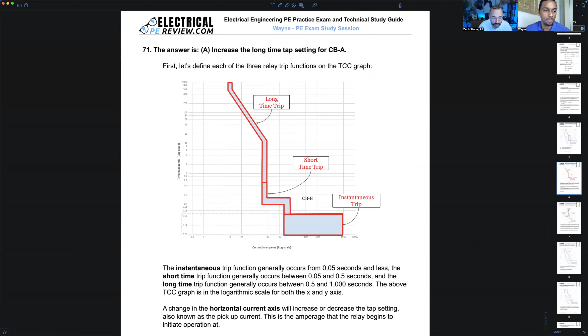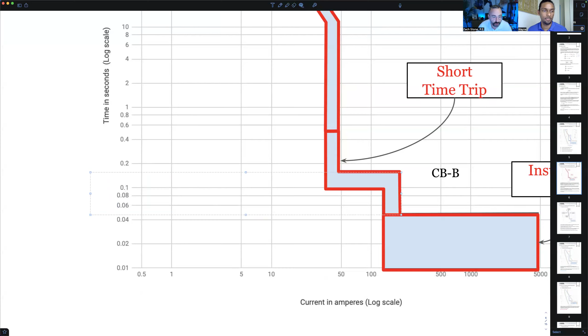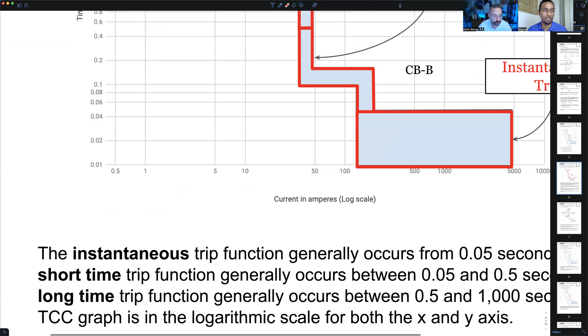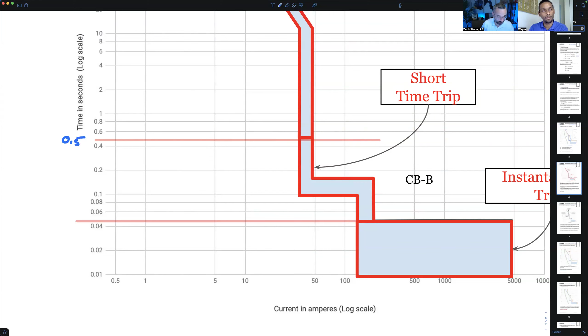So here's a good overview. Here's the instantaneous trip region, ending right here at about 0.05. Short time trip is 0.05 up to about 0.5 - right here, short time trip goes up to 0.5. That answers our earlier question of how high we could raise it. So the lowest for short time is here, 0.05, where instantaneous ends, and the highest would also be about 0.5, right about here. So that's our short time region.